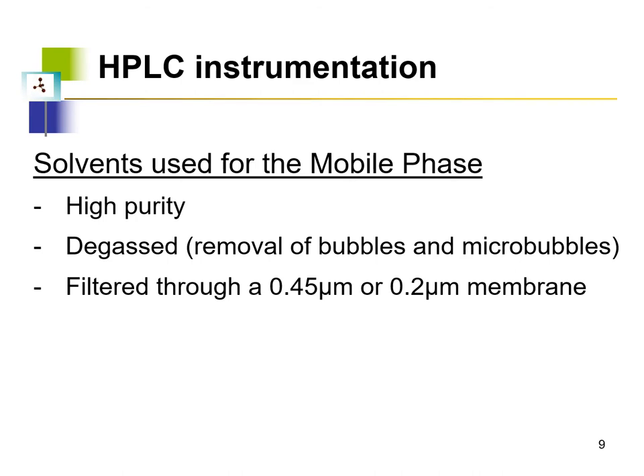HPLC solvents must meet certain criteria. First, they must be of high purity — 99.99% — because the solvent flows through a densely packed column, and even small contaminants such as metal ions can become trapped, damaging the column or causing high pressure buildup that damages the pump. For this reason, solvents are purchased as HPLC grade, meaning their purity is sufficient for use in the instrument.